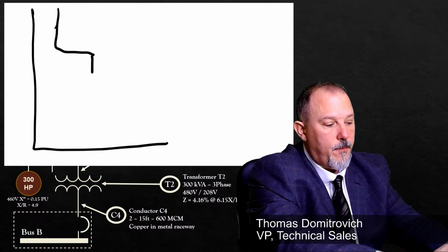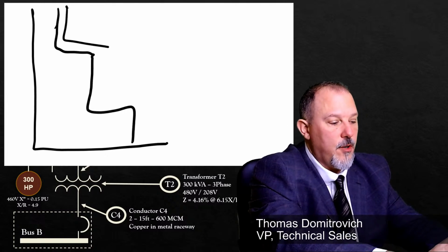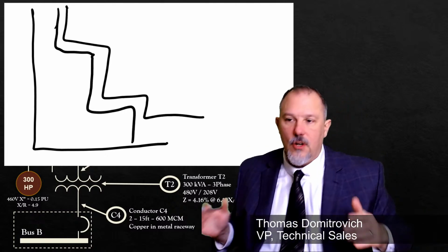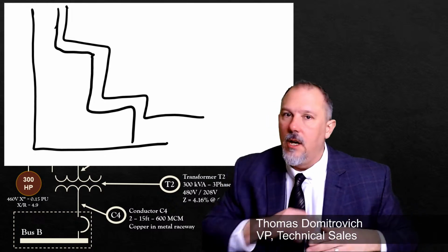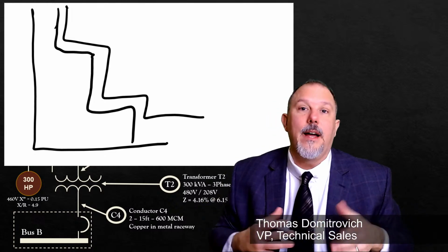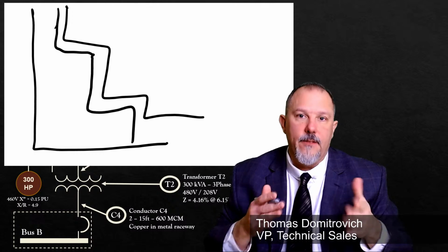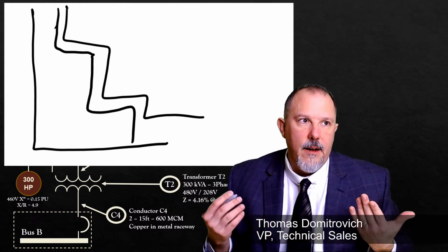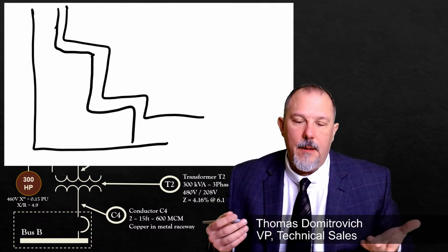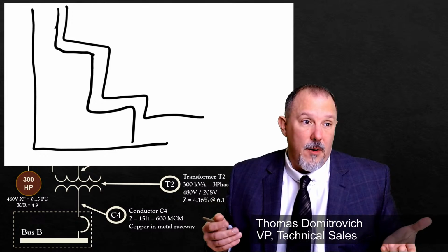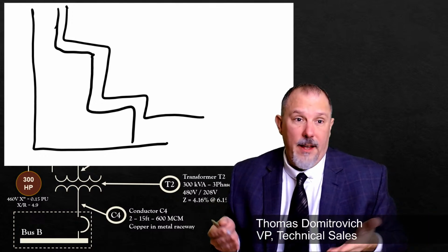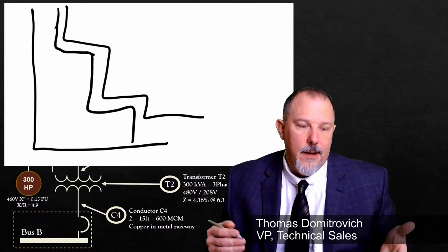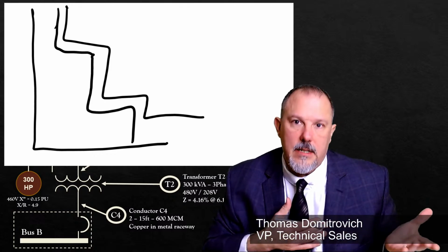Remember, a trip curve for an electronic trip unit. When am I going to see an electronic trip unit? I can have electronic trip units all the way down as low as you can go. I can have an electronic trip unit, but for a 30 amp breaker or a 50 amp breaker, 60 amp breaker, am I buying a molded case circuit breaker with an electronic trip unit? Heck no. Why not? Well, I can buy something a lot less expensive. Okay.